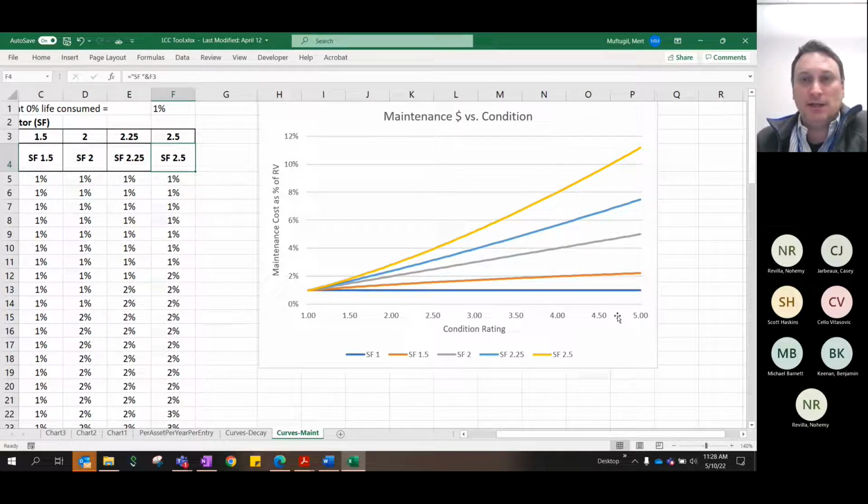In that case, there may be times when that cost increases over time, because of other things that are also deteriorating in the background, like the rate of decay of the impeller may be increasing as the asset builds more run hours. So that may actually be following more of an exponential curve.